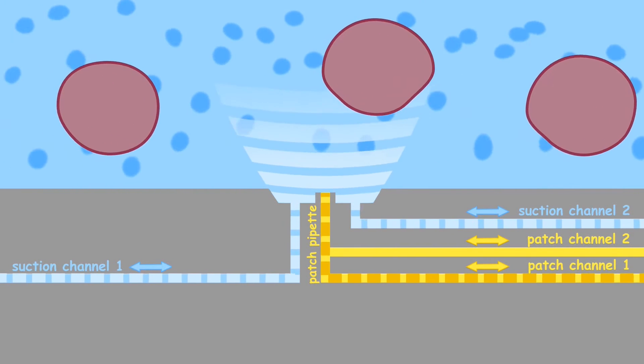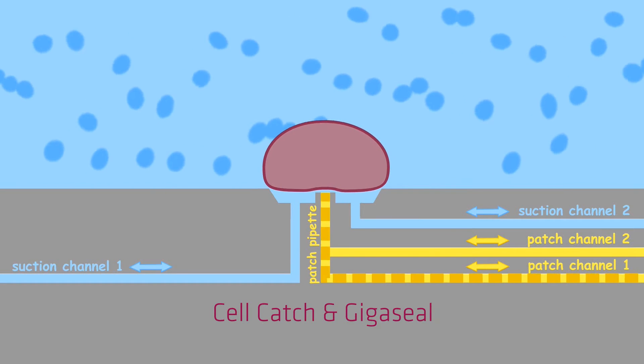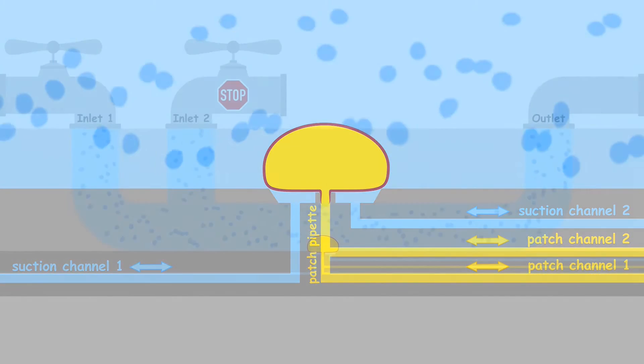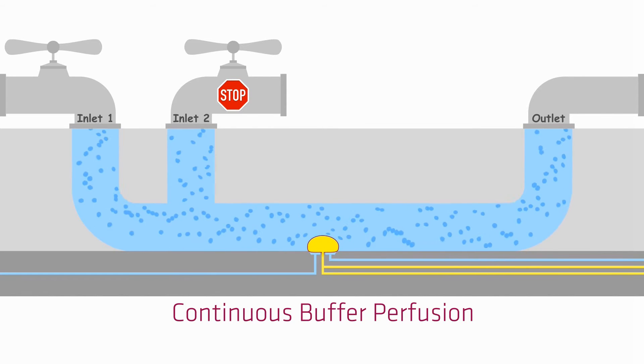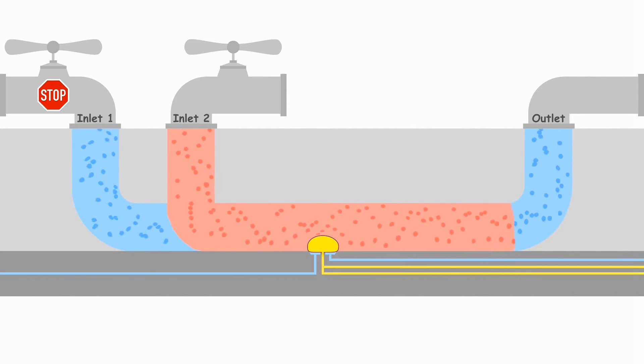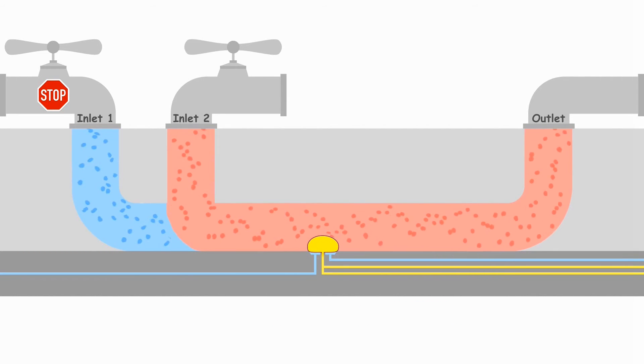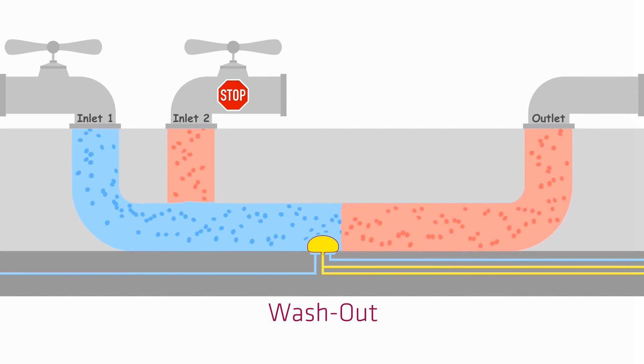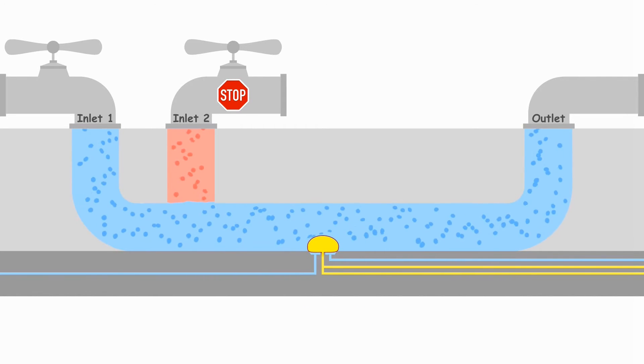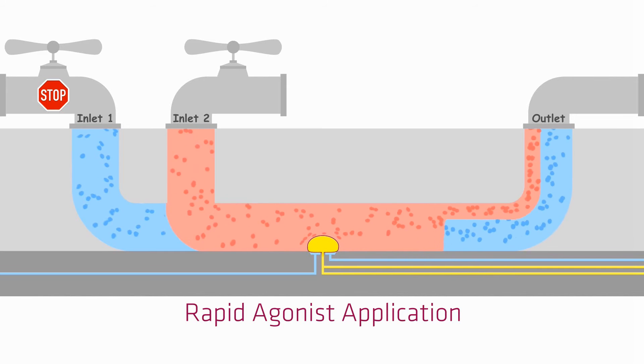And if you don't want to patch that cell for whatever reason, you simply flush it away and search for and gently suction the next one to analyze. This unique feature sets the Cytopatch apart from any other automated patch clamp system. The chip's perfusion chamber contains two independent inlets and an outlet channel for syringe and valve-controlled bi-directional flow in each. It is coupled with a small multi-channel amplifier and superior microfluidic perfusion logic, all controlled via a variety of features provided through the system software.